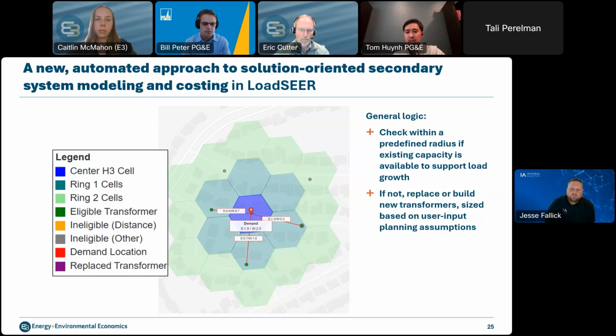Okay, so let's get into some details on the method, which in my experience is a lot easier to understand visually. So we have a visual here. The model steps through annual loads spatially, one at a time, and determines what the existing secondary transformer capacity is within this predefined radius. And then it allocates summer and winter coincident load proportionally to the existing transformers up to that defined maximum loading I mentioned before. And transformers are then replaced to accommodate the load, and that's subject to that size-up policy that I also mentioned earlier. And adding to that other secondary costs, like line extensions that are required.